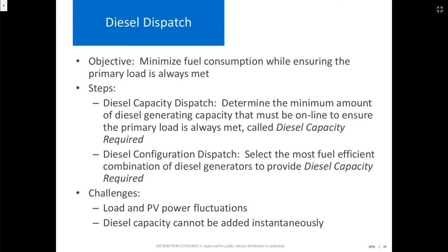A little bit on the diesel dispatch strategy. This is programmed to dispatch all of the available resources, TQGs, solar, battery, in order to optimize and minimize diesel fuel consumption. There's a couple of key parts to this, and there's always opportunities for add-ons to this dispatch strategy, but basically you want to make sure you've got some spinning reserve online. In an installation where there is no cube, you need to have, even if you don't need it, one backup generator always running. That results in folks often running two TQGs when they only really need one.